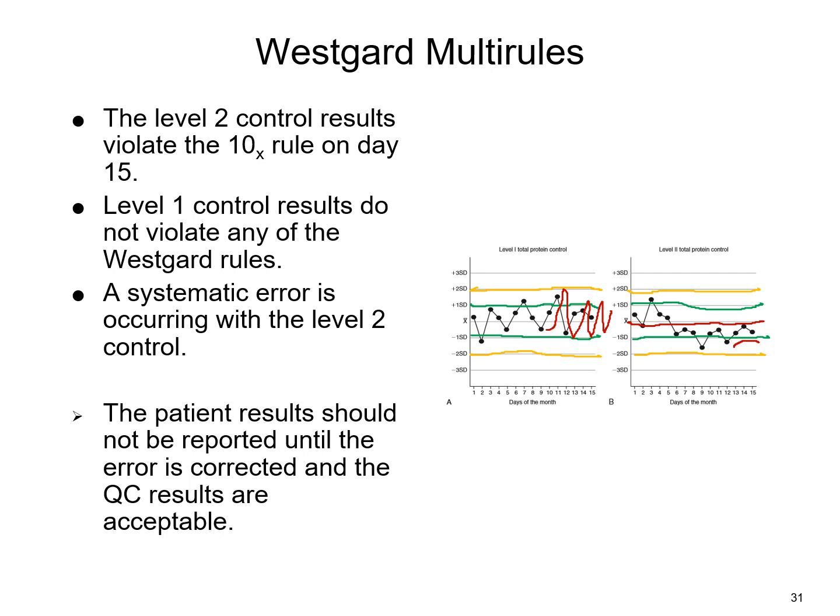Whereas the level 2, you can see that we have several values that are all on the same side of the mean. This means that there's some sort of systematic error happening within that level 2, and it could just be the quality of that level, because level 1 is doing as it should. So that doesn't lead me to believe that there's anything really major going on with the analyzer.